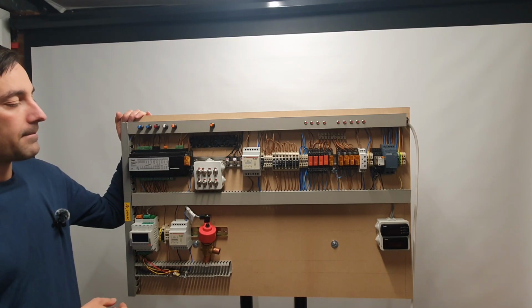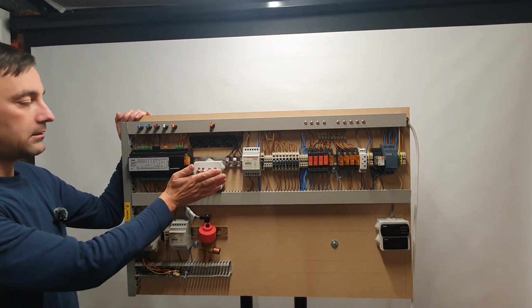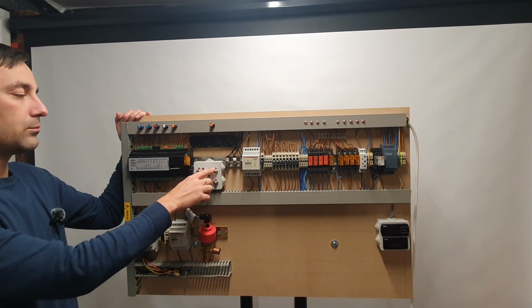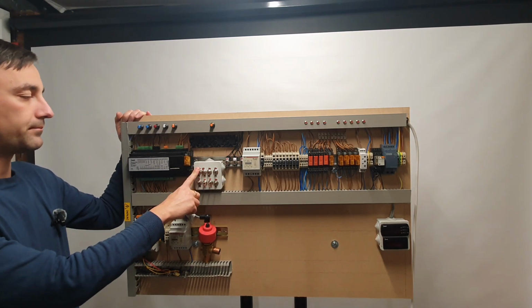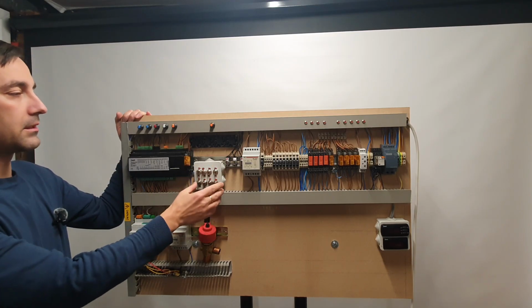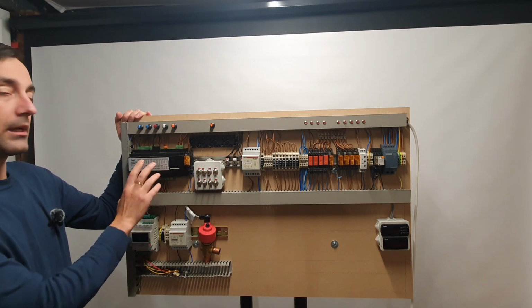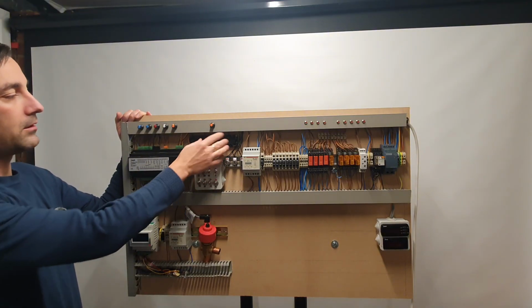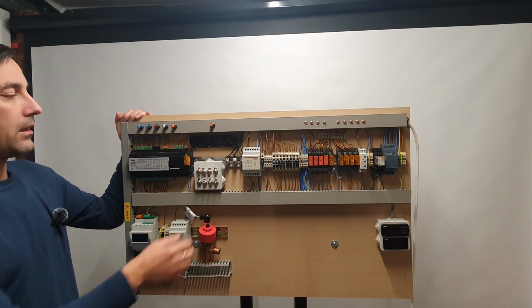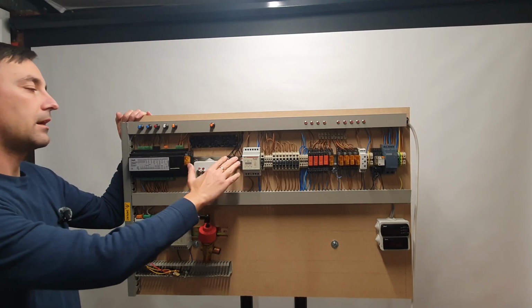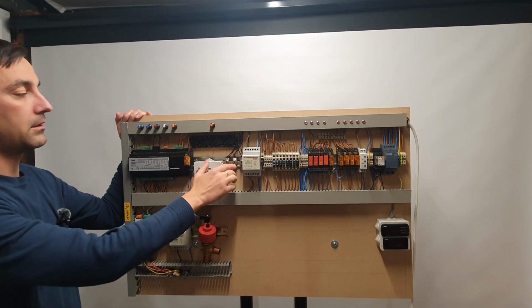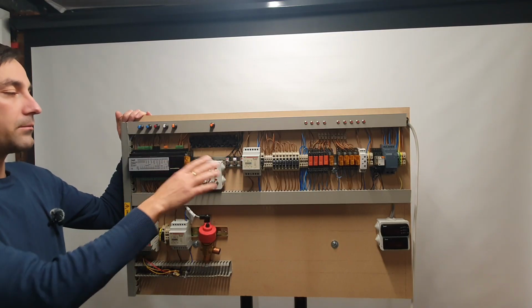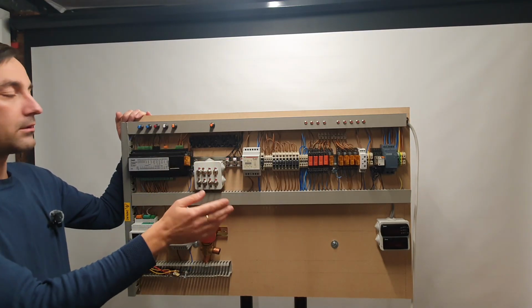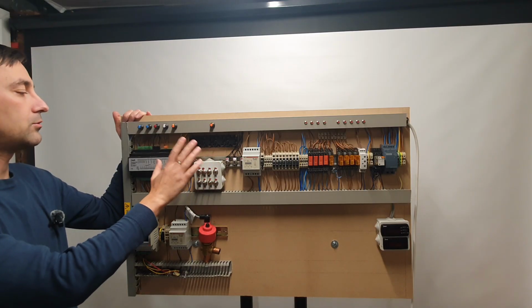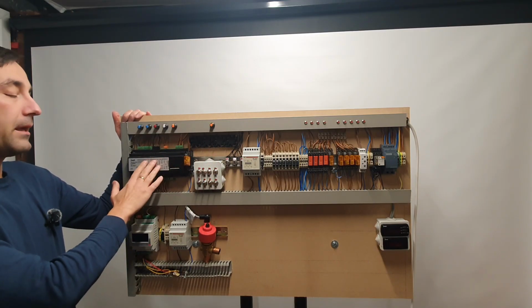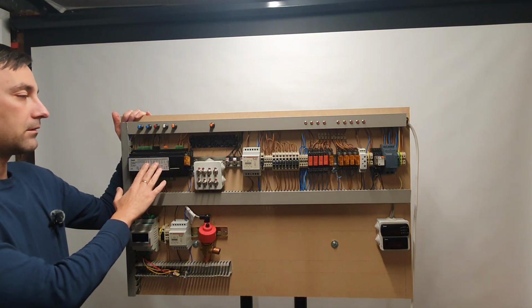Next, we have 8 safety switches, so these will simulate if a compressor is tripped. We have 8 because I decided to use 8 compressors. We have 4 condenser fans. We have 3 safety switches. They are not compressor trips, but they can be an HPLP shutdown, a low liquid level, or anything we want it to be, depending on what the controller can offer.